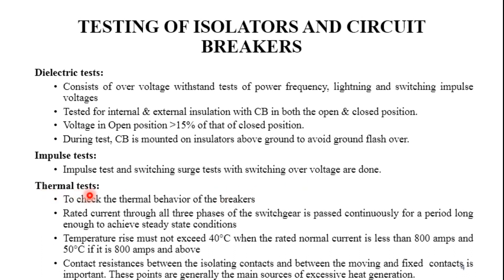The thermal test and mechanical test are type tests on the circuit breaker, conducted according to specification. For the thermal test, the temperature rise must not exceed 40°C when operating under rated normal current of less than 800 amperes, and must not exceed 50°C for 800 amperes and above. These are the different types of tests conducted on isolators and circuit breakers.